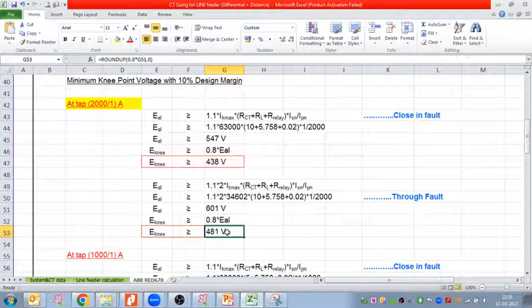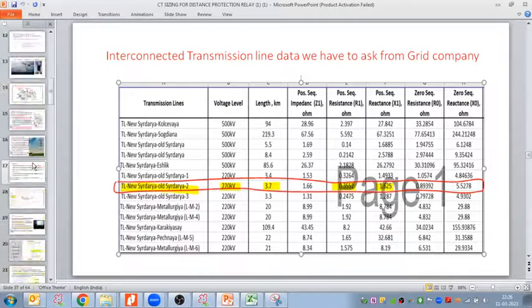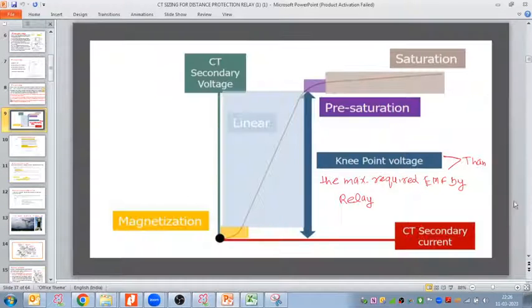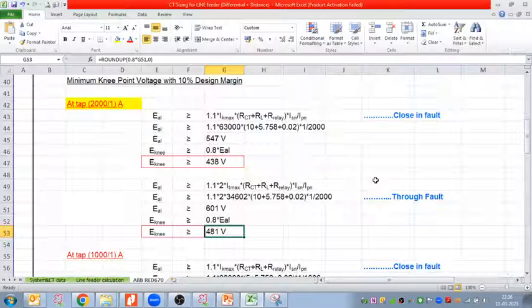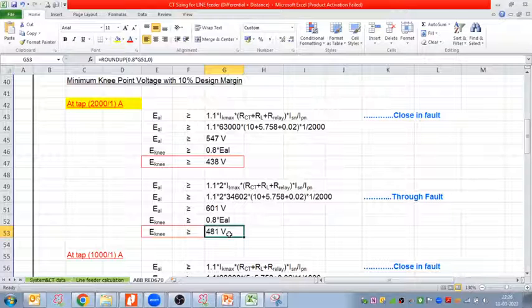So 481 voltage, this CT knee point voltage should be higher. Out of these two, which one is the higher? 481 is higher, so that should be the minimum available knee point voltage. If we go to the CT saturation curve, this voltage should be greater than how much? 481. This is for the closing, for the line differential protection case, right?